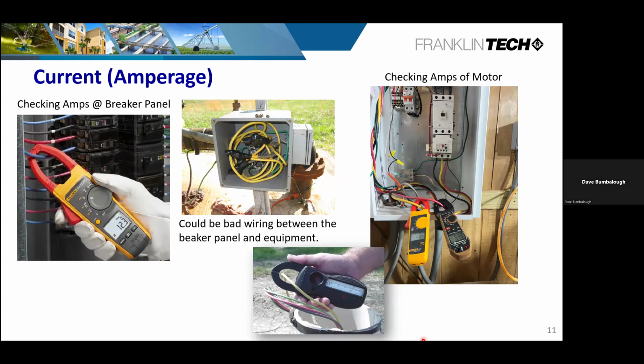One other thing that amp meter can do for you is trace down issues. So if we are having nuisance tripping at our controls, then we can try to backtrack and see if there is something else contributing to it. Let's just say we've got a breaker over here in the panel that keeps tripping. We look at it, and it may be pulling 12 amps, let's say it's a 20 amp breaker and it keeps tripping. We know that our equipment over here may be pulling the 12 or 13 amps that it was designed to run at, but then the 20 amp breaker is tripping. There may have been somebody who piggybacked off a junction box and borrowed the power to put a light on, or a receptacle, or maybe even a secondary pump pulling off that same supply, and hence the reason for the nuisance tripping.